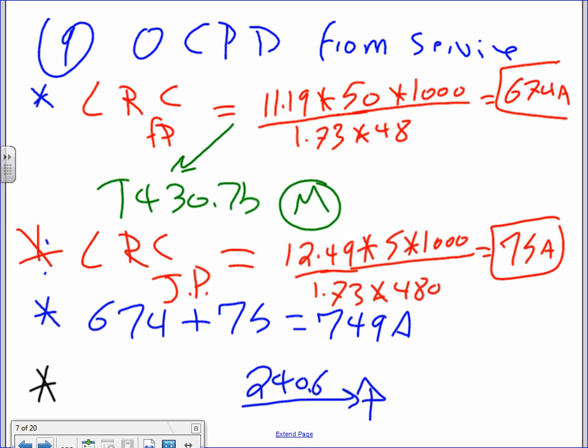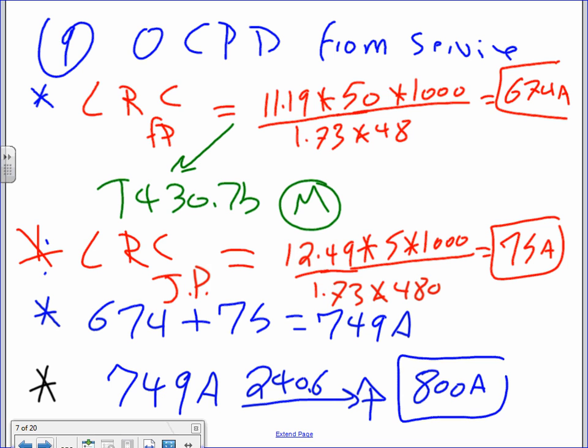Find the full load current, add them up. Then take the 749 amp, take it to 240.6. If it's not a standard amp, you're going to go what? We're going up. And the sheet will tell you. This is an 800 amp circuit breaker.